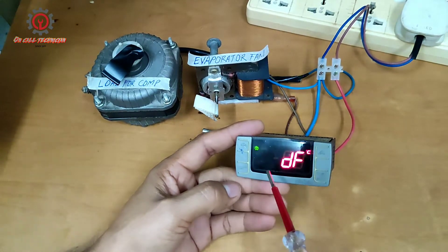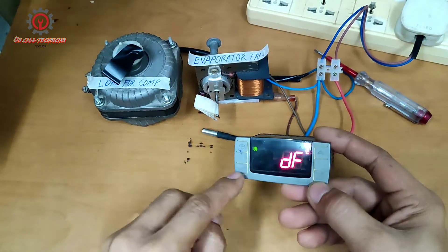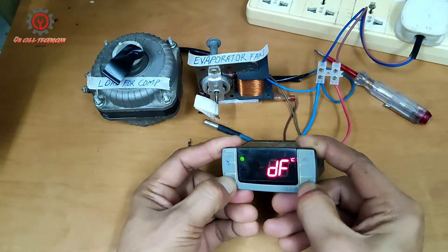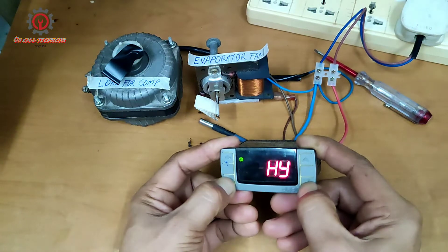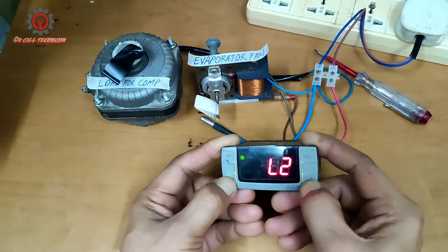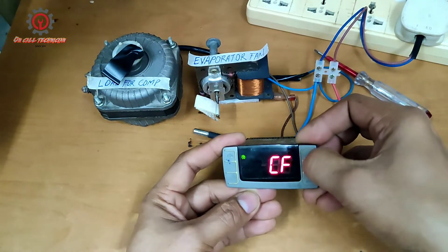To do that, I set DD to electrical, and then we press the Set and Add Down button for three seconds, and another Set and Add Down button for seven seconds to enter the hidden parameter. Then let's proceed to CF — CF is the fan management.